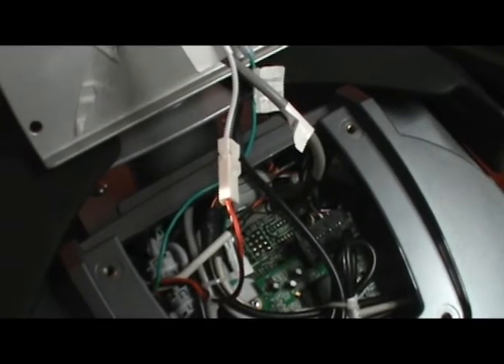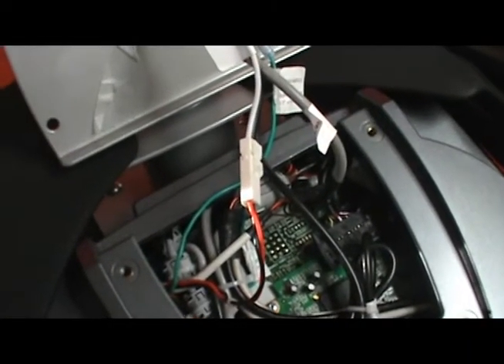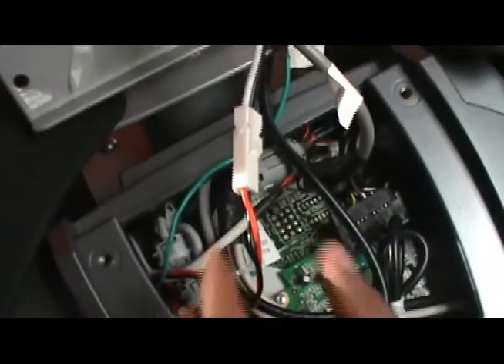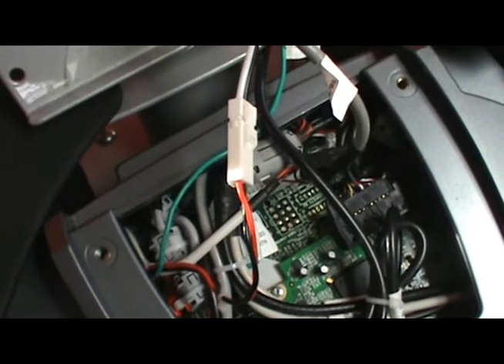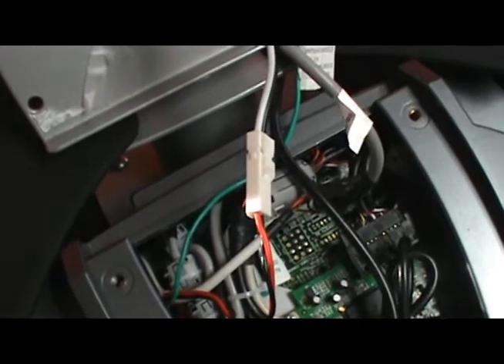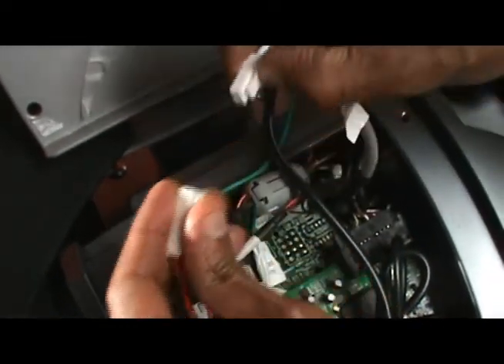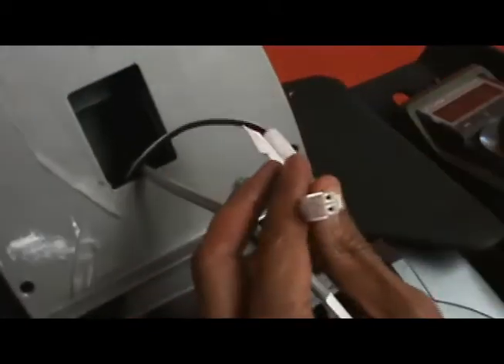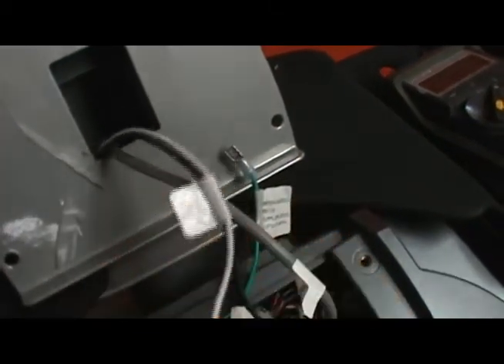Now that we've got the console off, you'll see the connection that comes right up through the neck, and this is where we get our power going to the console. We're going to disconnect this connection and take a DC voltage reading between the black and white cable to verify we've got voltage coming up to the top.